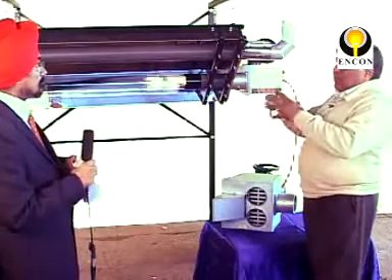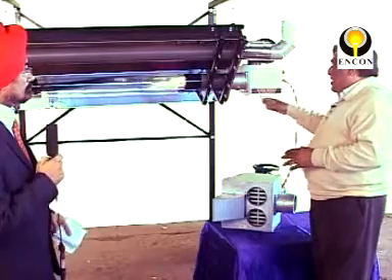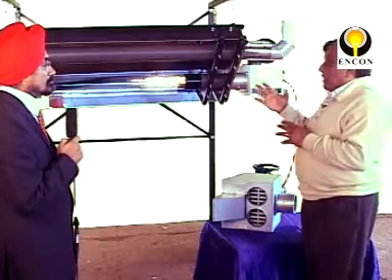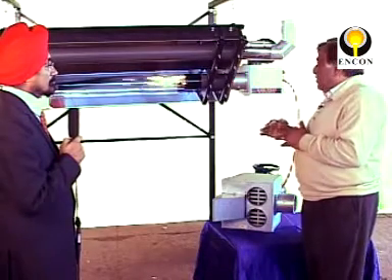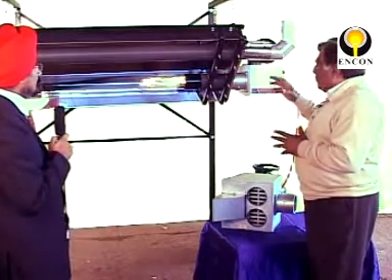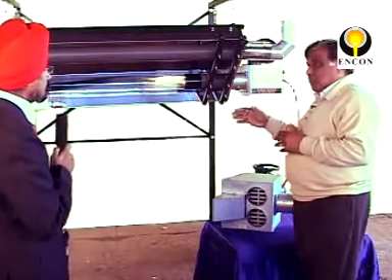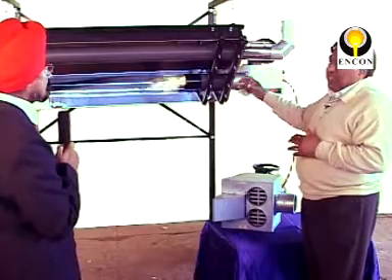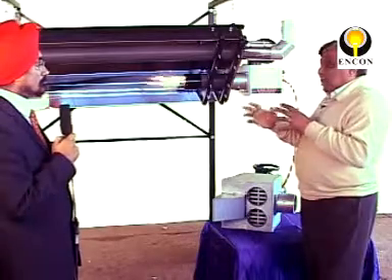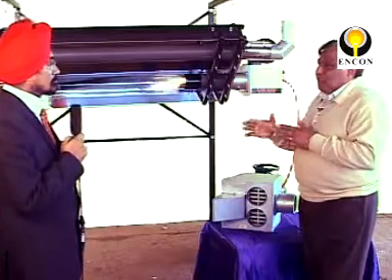There is a vacuum proving switch — till the time there is a vacuum in the system, you don't get the firing and you don't get the gas in the system. At around minus 0.3 mm — it can vary depending on the length of the tube and the system — once the vacuum is created, a solenoid valve (fast opening, fast closing) actuates. Once we see that the flame is established, a second solenoid valve opens. The system has a double block of solenoid valves, which has a very high level of safety factors approved worldwide.